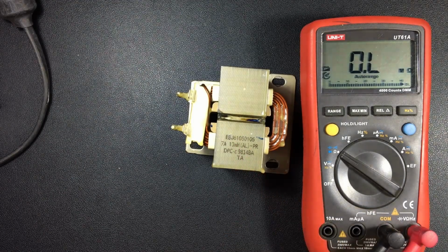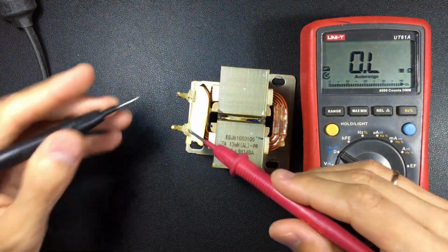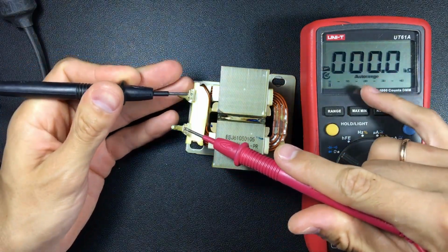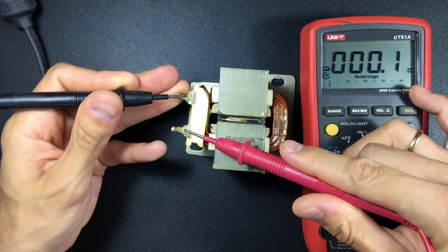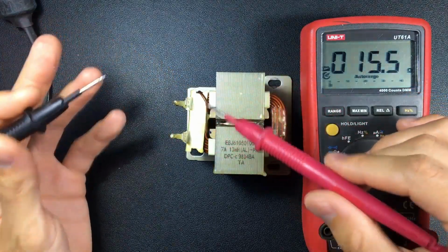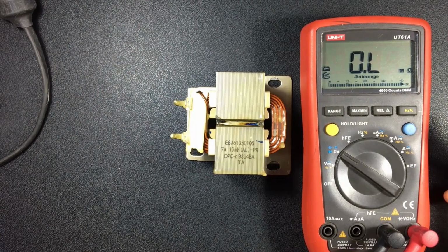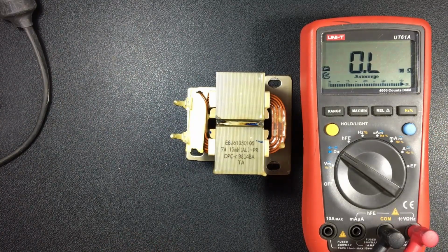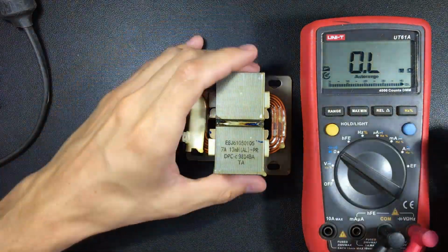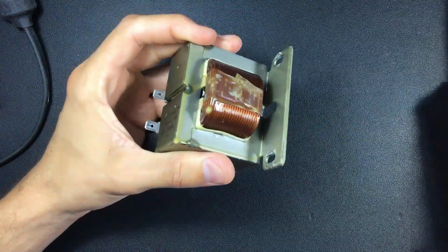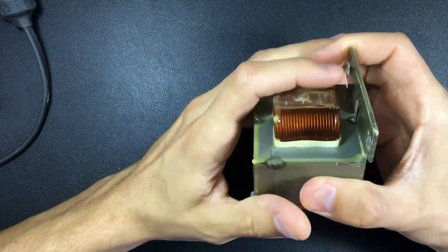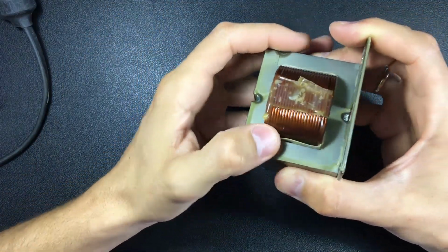You have to understand it, because you understand the operation. And of course, any technician looks here and finds a resistance perhaps of 2 or 3 ohms and says, well, this is fine, it has continuity, but 2 ohms is too much, there has to be less. And there is the problem. If this becomes faulty, it can be due to several reasons. For example, it got wet and went into a short circuit.